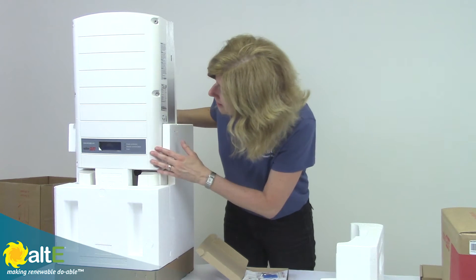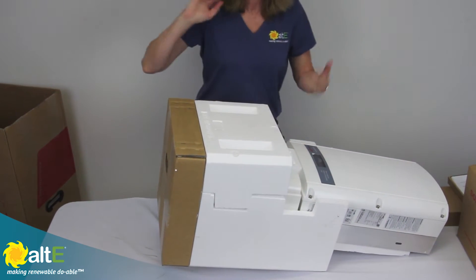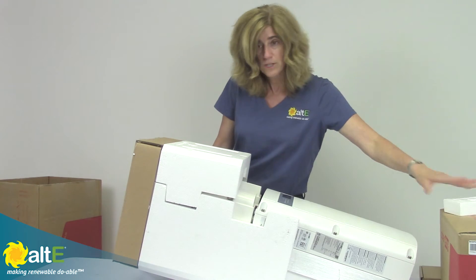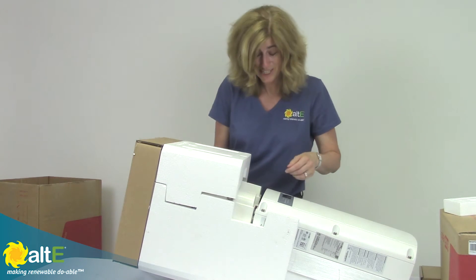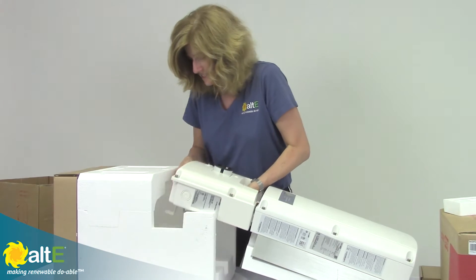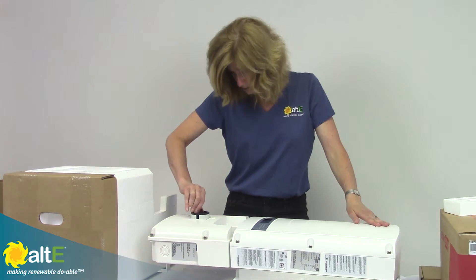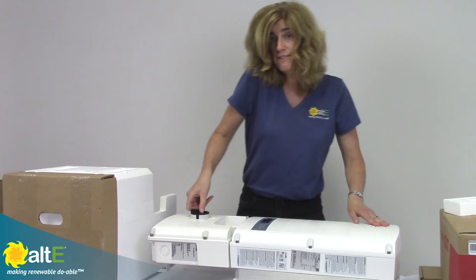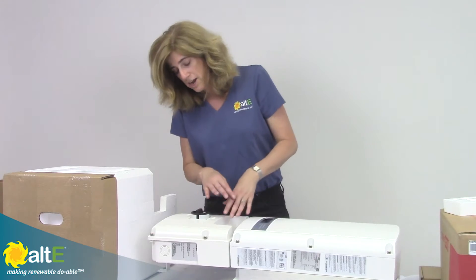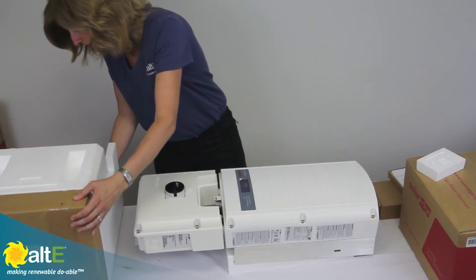You can see here that we've got the inverter itself with a nice display. It is transformerless, so although it's not incredibly lightweight, it is fairly lightweight — anywhere from 51 to 88 pounds depending on the model. That's a nice difference from the old transformer inverters that need two people just to move. It's got a separate DC disconnect right here, a nice switch to turn on and off the DC right at the inverter. It's got the glands in here for easy wiring, and some nice knockouts at the end for all the wiring, making it a really clean install.